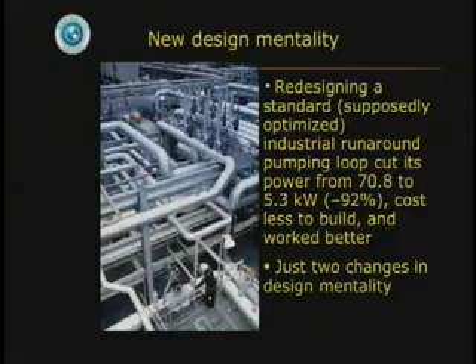The first was to use big pipes and small pumps rather than small pipes and big pumps. The friction in a pipe goes down as nearly the 5th power of its diameter. So how big should the pipe be to optimize its friction? All the textbooks we've found say you should make the pipe just as fat as will repay its greater capital cost over the years out of the saved pumping energy, which sounds perfectly logical—you don't want to pay more than it's worth, do you?